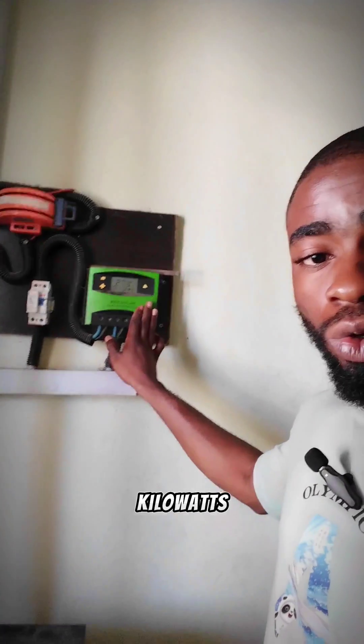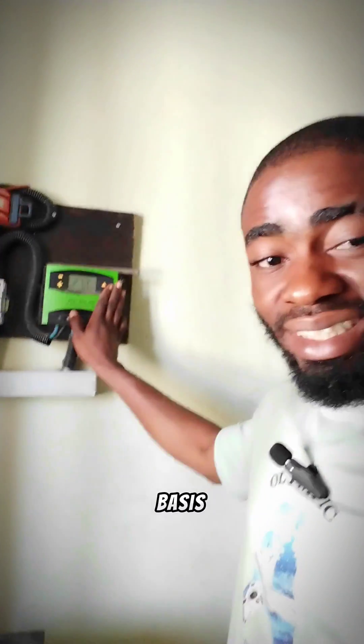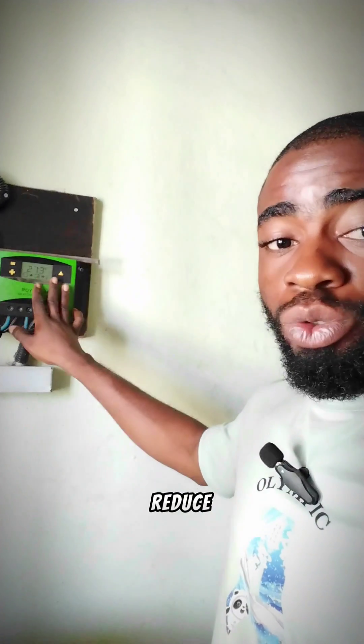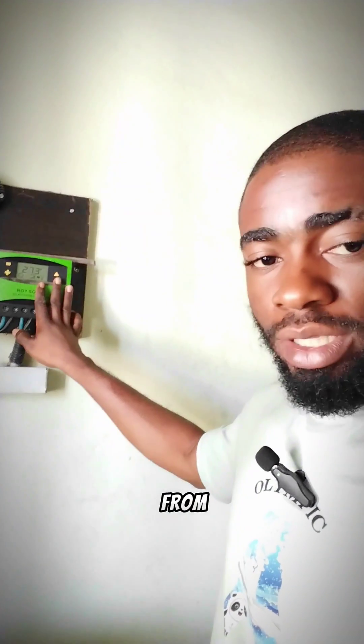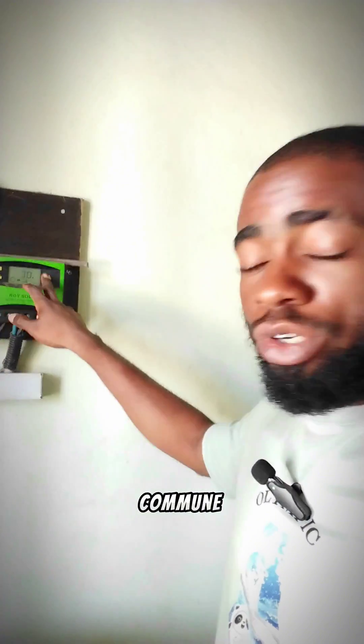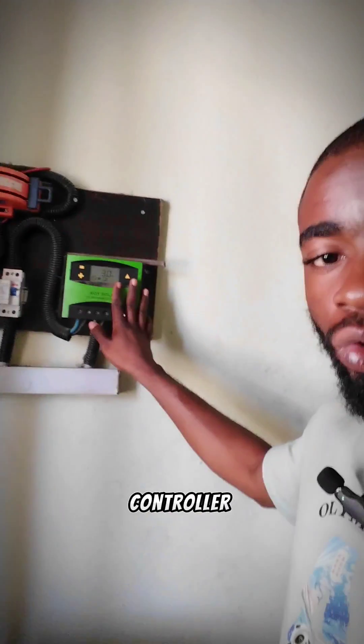On the roof we have 1.2 kilowatts of solar energy coming to this solar charge controller on a daily basis. This charge controller is not heating at all. It will reduce the current coming from the solar panels to keep the battery at float charge — the maximum current coming right now is just 3.0. And once this battery goes below maybe 23 or 24 volts, immediately this solar charge controller may allow around 20 to 25 amps to pass. That is how a PWM works.